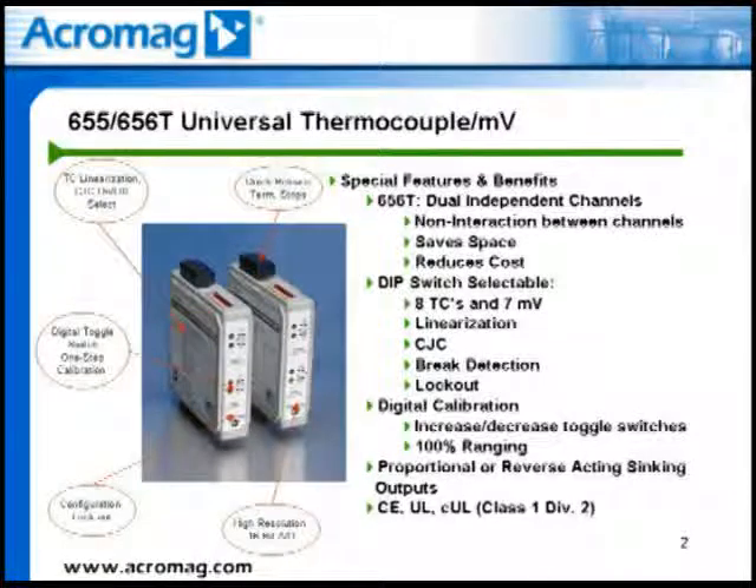Configuration for the 655T and 656T transmitters is simply accomplished through DIP switch settings. DIP switch settings include eight different thermocouple sensor types or seven different millivolt ranges for optimum accuracy and resolution, linearization to millivolts or temperature, cold junction compensation on or off, thermocouple break detection on or off, and when on, can send the signal either upscale or downscale, and finally a setting to lock out the configuration.